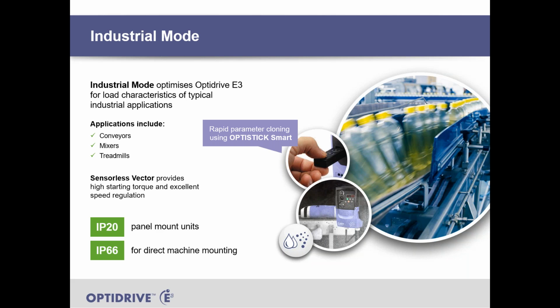We can also use the OptiStick Smart, so the Bluetooth interface, as a parameter copying function as well, a parameter cloning function. So if you've got an OEM that does the same thing, the same function with drives multiple times, then they can have one setup in the OptiStick and just download it to the drive very, very quickly.